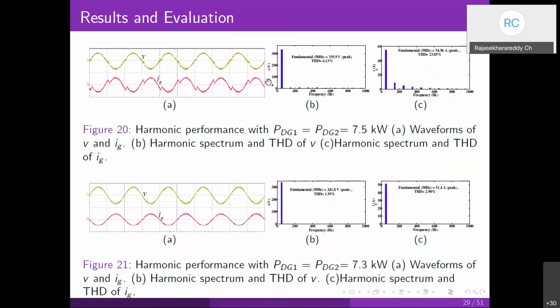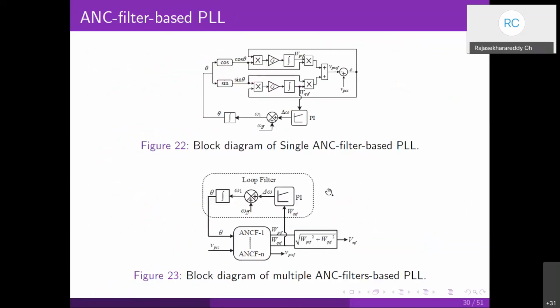When both the inverters are fully loaded with active power generation, they are not giving any harmonic currents compensation. We can see the distortion in the PCC voltage, and consequently we have THD of voltage of more than 6%. When both the inverters are providing compensation, you can see an improvement in PCC voltage, and the THD is about 2% for grid voltage. That is about the multifunctional nature of our DG sources.